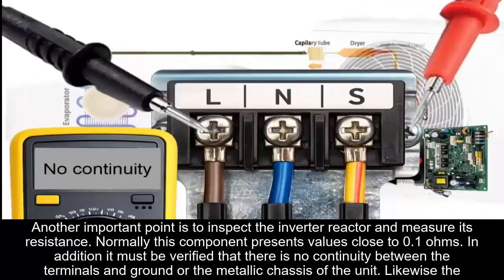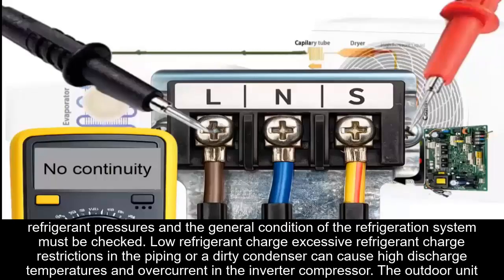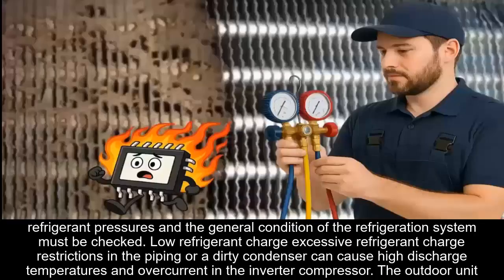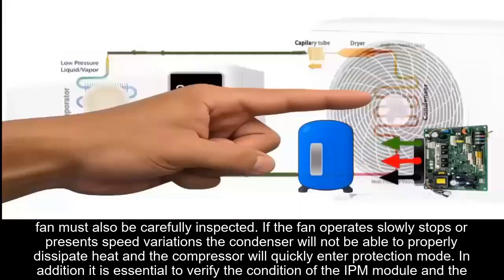Likewise, the refrigerant pressures and the general condition of the refrigeration system must be checked. Low refrigerant charge, excessive refrigerant charge, restrictions in the piping, or a dirty condenser can cause high discharge temperatures and overcurrent in the inverter compressor. The outdoor unit fan must also be carefully inspected. If the fan operates slowly, stops, or presents speed variations, the condenser will not be able to properly dissipate heat, and the compressor will quickly enter protection mode.